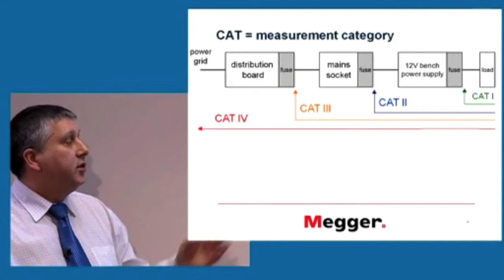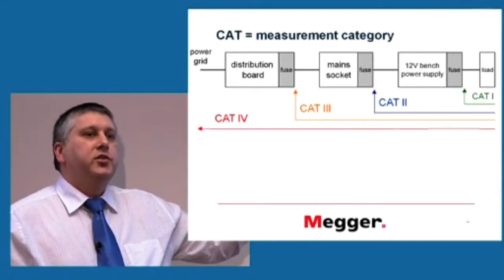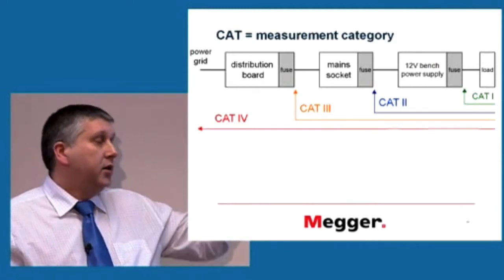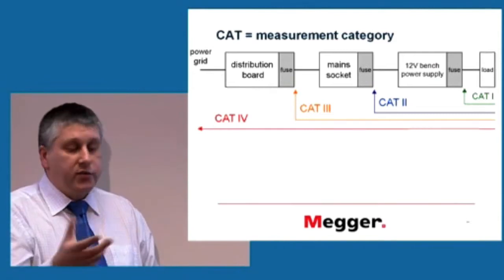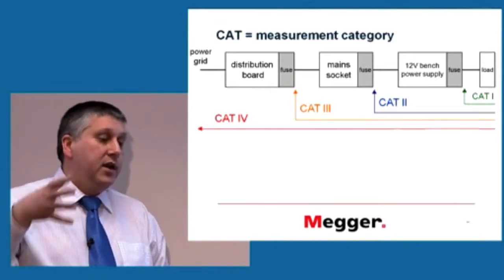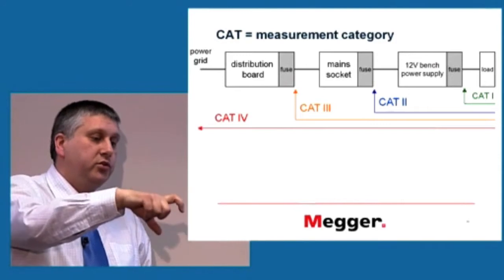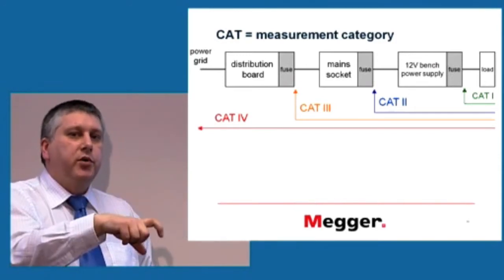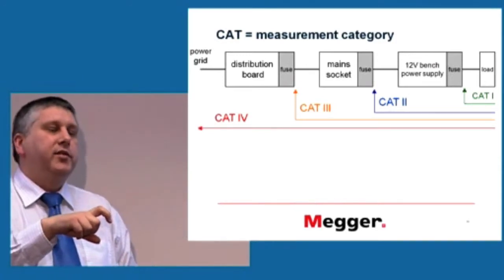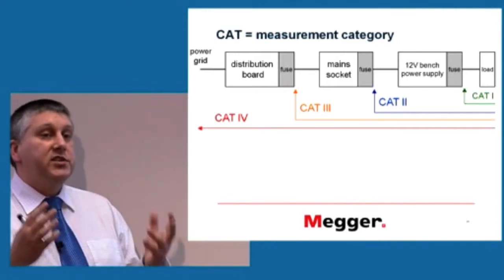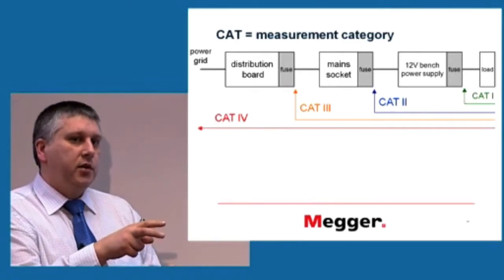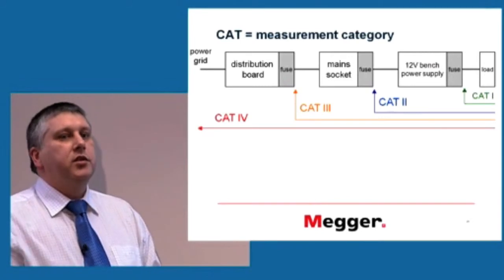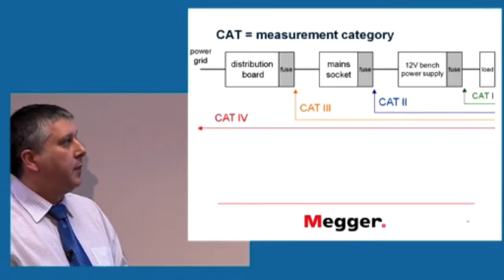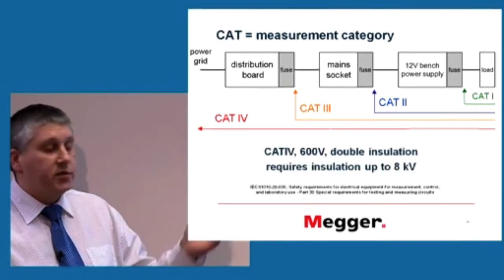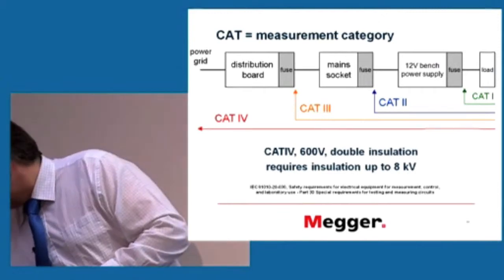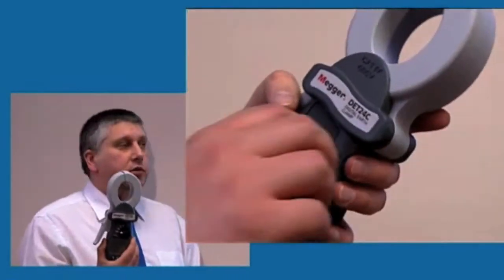So we are potentially exposed to very high energy. Whatever the transformer can give us, it will be there. So if we clamp our current transformer around something in such a way that will short two conductors, they would be exposed to very, very high energy levels. And the device has to be designed to either contain that energy or to make sure we are not short-circuiting the two conductors.